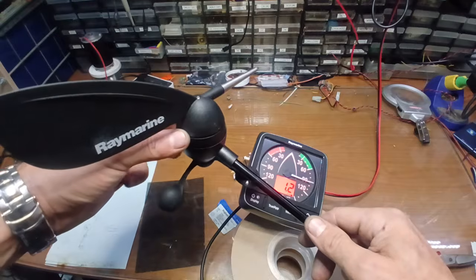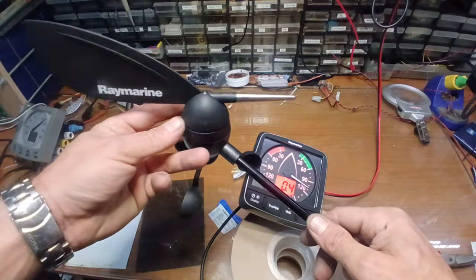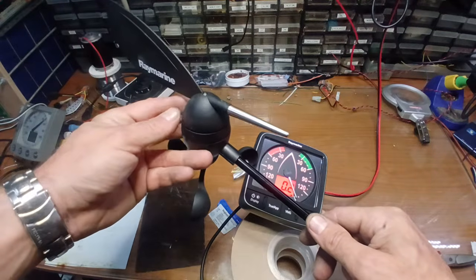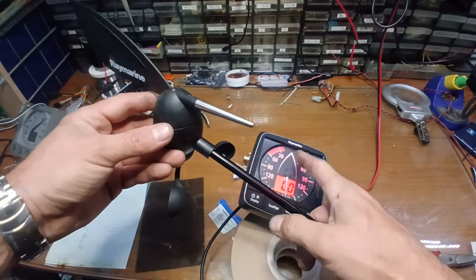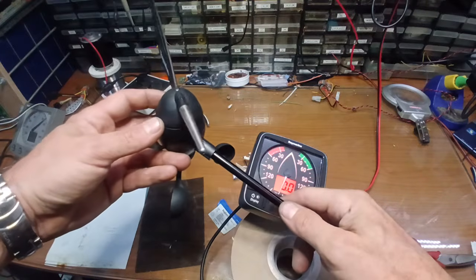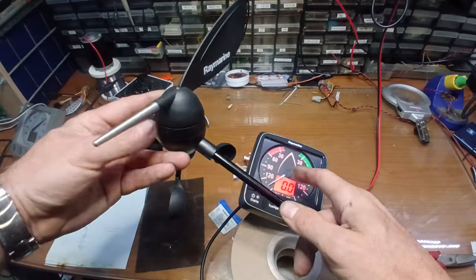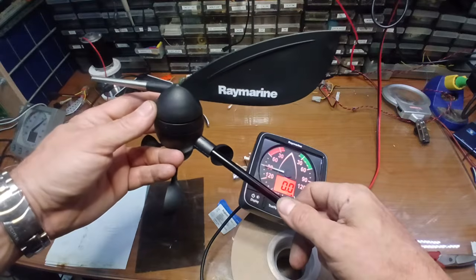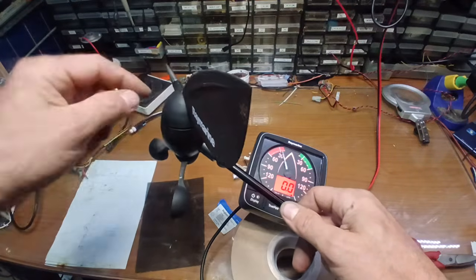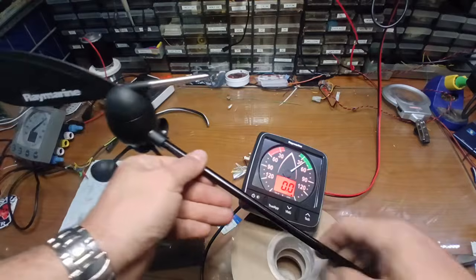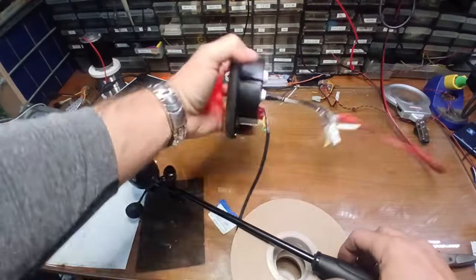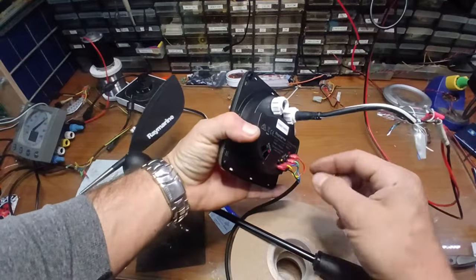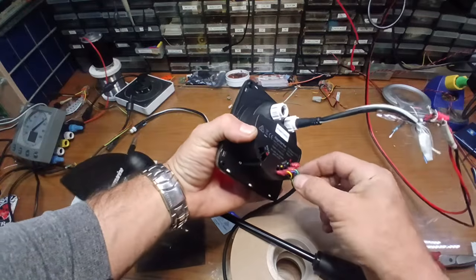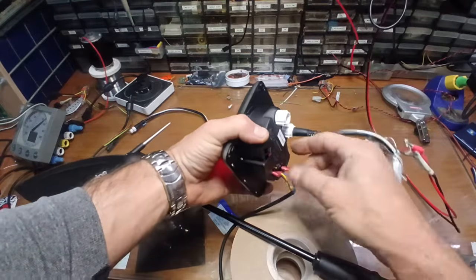In order to know if the instrument is working fine, do a 360 degrees and make sure the needle follows all 360 degrees. Because a lot of times, at the foot of the mast, inside the board, or on the cable, there is a problem where one of the two, either the sine or cosine, the green and blue, are not connected.